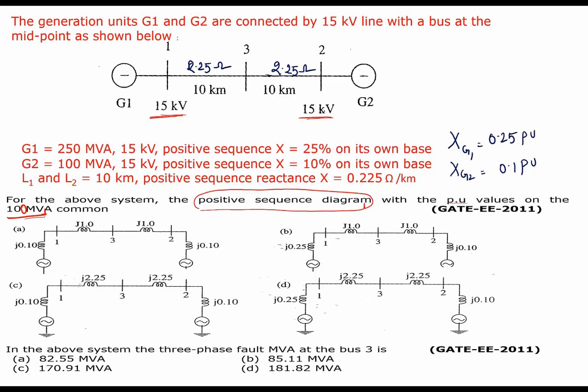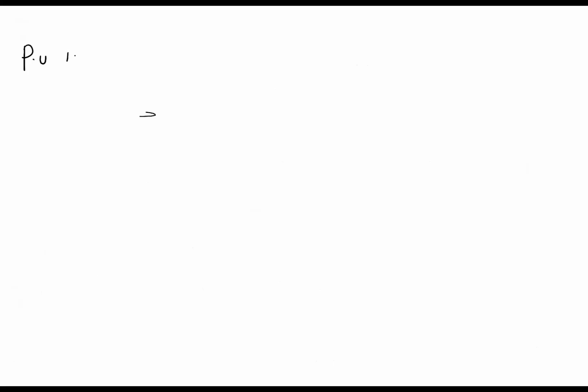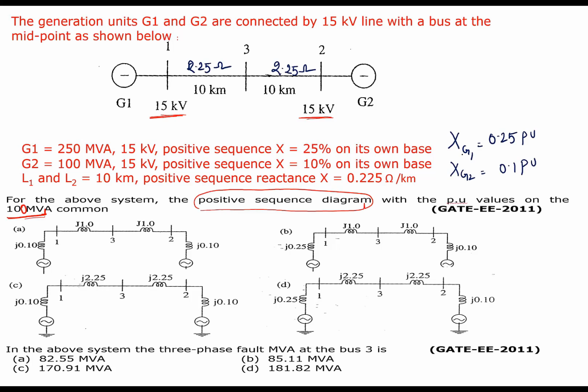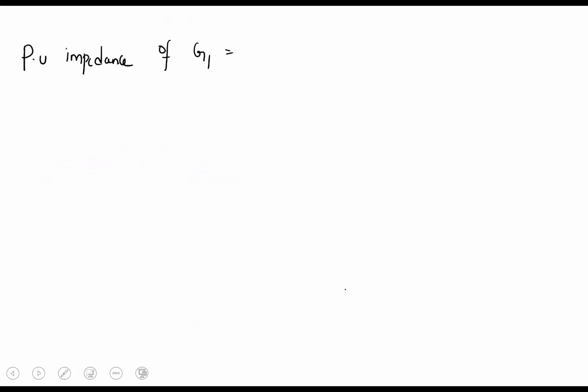Okay. Now the per unit impedance of generator G1. I'm directly writing the per unit impedance of generator G1. Already we know the per unit value of this one on its own rating is 0.25, but the machine MVA rating is 250 MVA. Voltage is same, no issue. So our new MVA rating is 100. So you're going to get 0.25 multiplied by new base MVA 100 divided by old base MVA, that is machine MVA, 250. Both base voltages are 15 squared. So you're going to get j0.1 per unit.